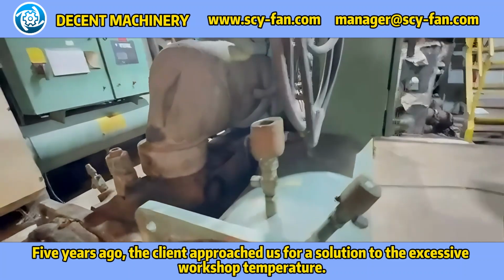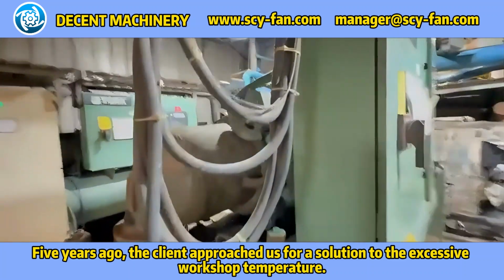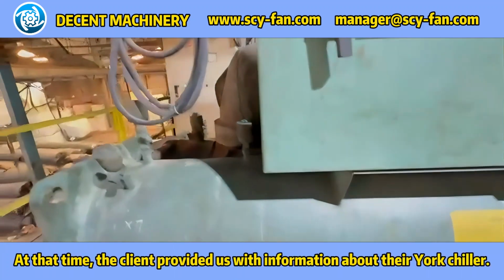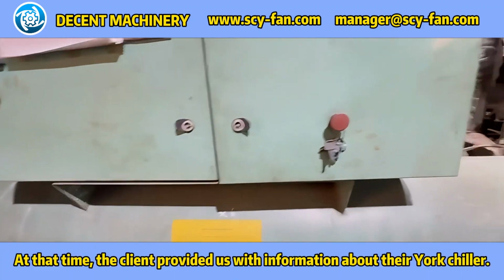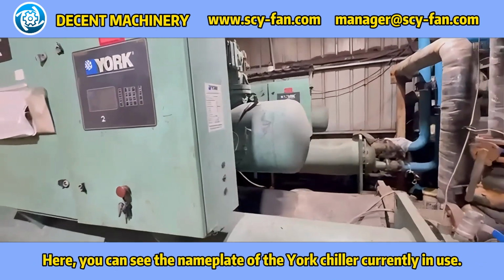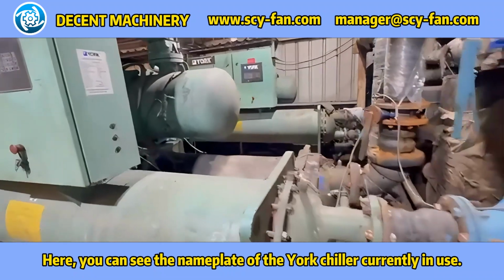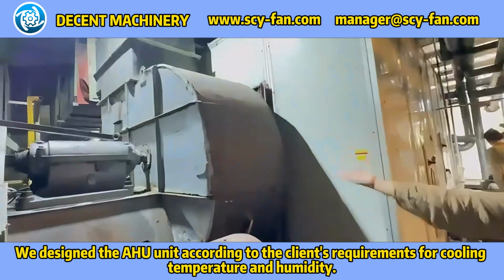5 years ago, the client approached us for a solution to the excessive workshop temperature. At that time, the client provided us with information about their York chiller. Here, you can see the nameplate of the York chiller currently in use. We designed the AHU unit according to the client's requirements for cooling temperature and humidity.